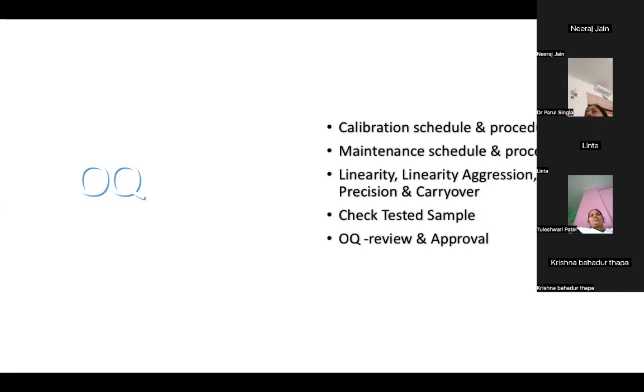If they are doing creatinine and beta HCG, the criteria will be different. For creatinine, acceptable variation may be 5%, but for immunoassay, it may be 7% or 10%. So ask for the passing criteria of the analytes they are checking in this report. Tell them to make a report along with the raw data, then review and approve it. It should be signed by the engineer or the application specialist and the authorized person of the lab. This is the operational qualification.